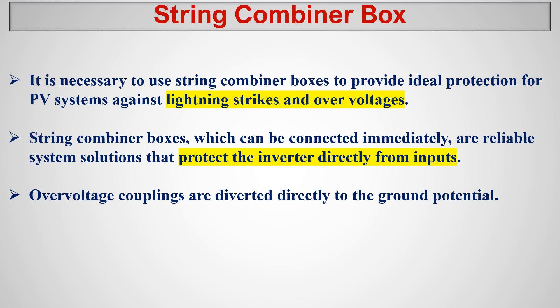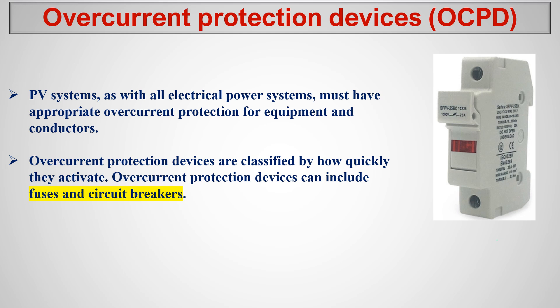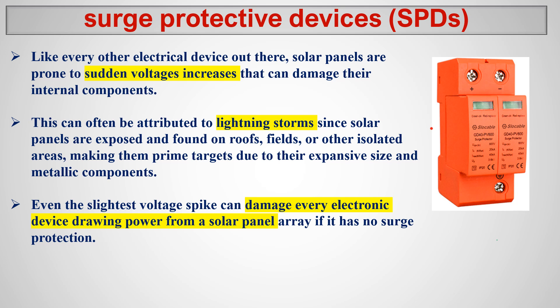Over-voltage surges are diverted directly to the ground if any lightning strike or over-voltage occurs. We also have an over-current protection device — a circuit breaker or fuse. For very low amperage we use fuses; otherwise we use circuit breakers. Circuit breakers limit the current; for example, if 10 amperes is my maximum current at maximum power point, we don't want more current coming out of the string, so we install a circuit protection device.